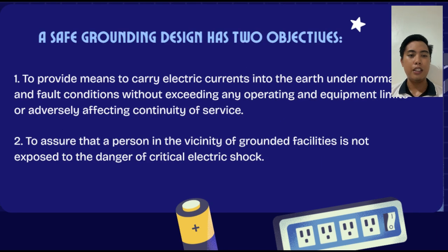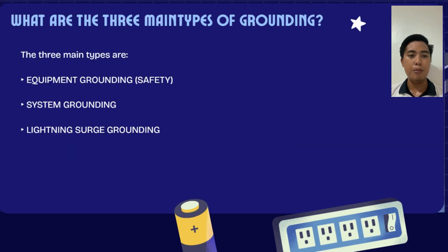A safety ground has two objectives. First, to provide means to carry electric currents into the earth under normal and fault conditions without exceeding any operating and equipment limits or adversely affecting continuity of service. Second, to ensure that a person in the vicinity of grounding facilities is not exposed to the danger of critical electric shocks. What are the three main types of grounding? The three main types are equipment grounding or safety grounding. It protects people from electric shock by connecting the metal parts of appliances to the earth. If a fault occurs, current flows safely to the ground instead of through a person.